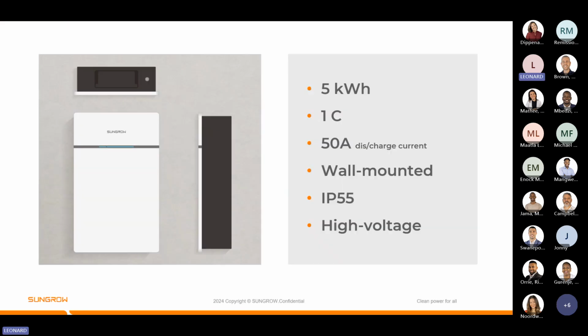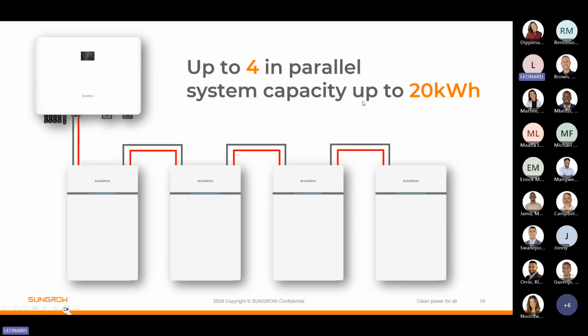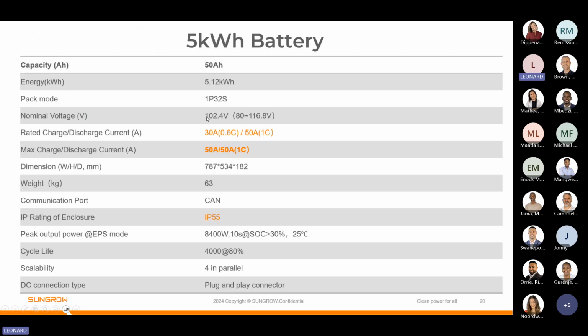Then in terms of the new battery that we are planning to release, it is a 5 kWh solution. This will be a 1C application with 50 amps charging and discharging, and it will also be wall mounted with IP55 rating, and it will also be a high voltage solution similar to our other solutions. So you will also be able to parallel 4 of these batteries, adding up to 20 kWh. This is just our approach towards 1C applications in South Africa, which will also be much more cost effective compared to our normal 0.7C solutions. But the downside is obviously this is not modular compared to our SPH and SPR solutions.